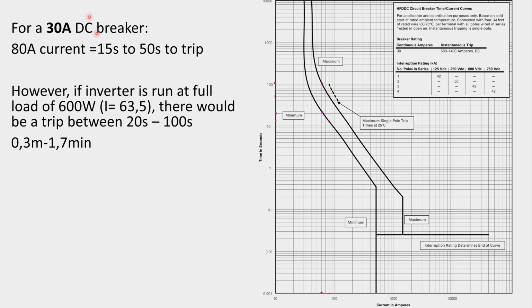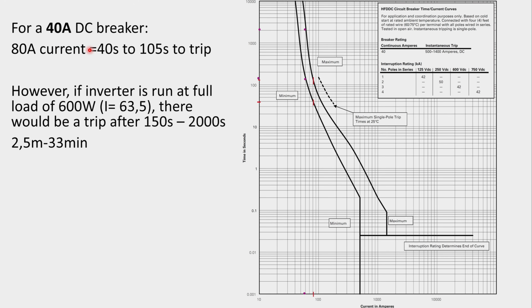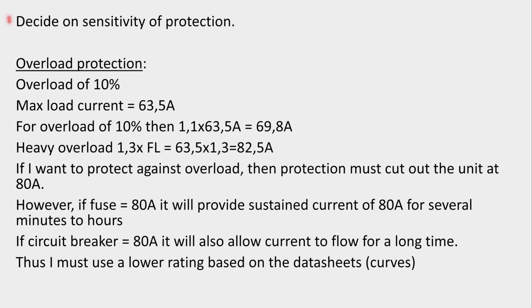Another reason why I don't want to use a 30 amp or a 40 amp circuit breaker is what happens if I connect a floodlight to it or something that has that very high rise in current, that inrush current. I don't want the circuit breaker to keep tripping when the inverter should be able to handle it. Now, keeping in mind that this, again, is based on one's decision.